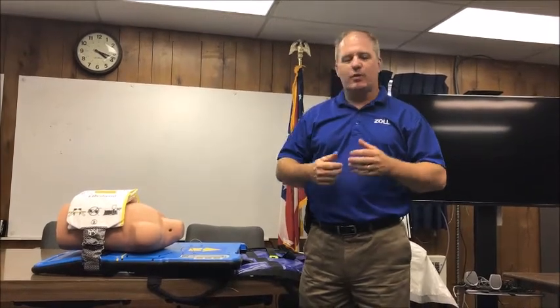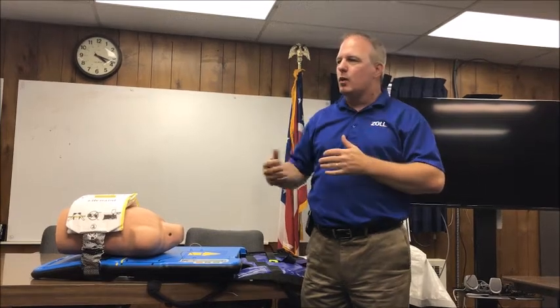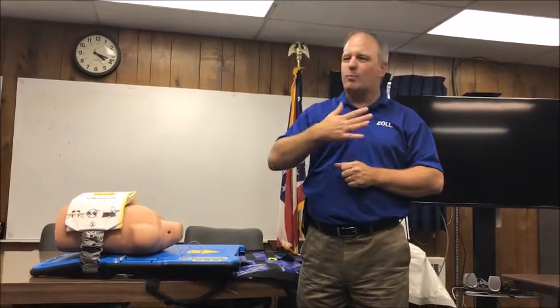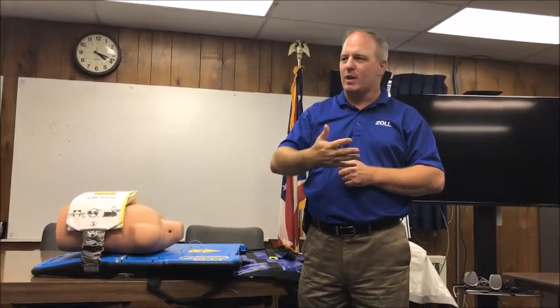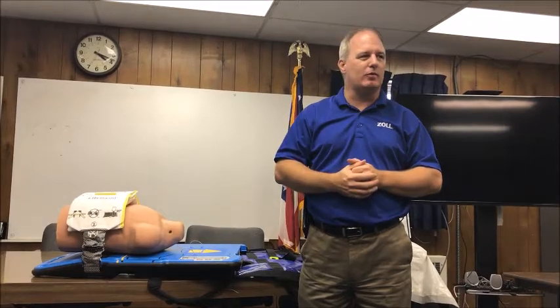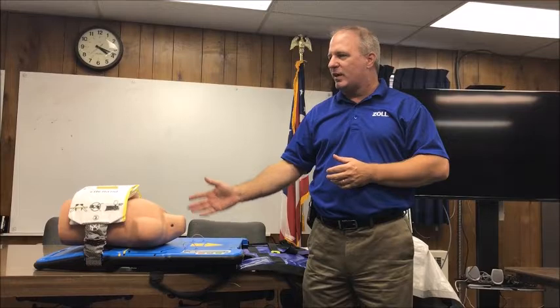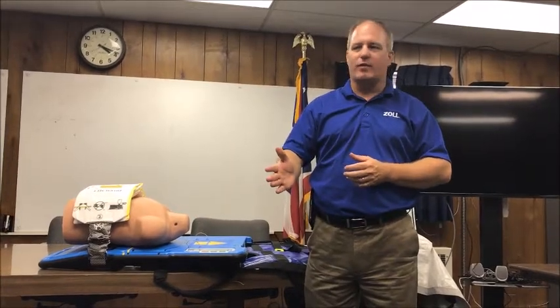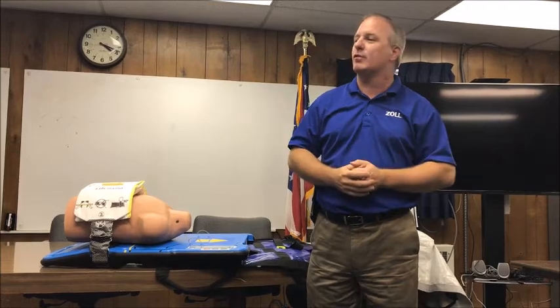And as a result, where the AHA guideline is 2 inches at 100 compressions a minute, we don't go quite 2 inches, we go 1.82, and we do not do 100 compressions a minute, we do 80. But we're still able to move much more blood volume than typical CPR. It's just a different way of doing things. The AHA addresses both this and the LUCAS device in the 2015 guidelines by saying refer to manufacturer recommendations for those devices.